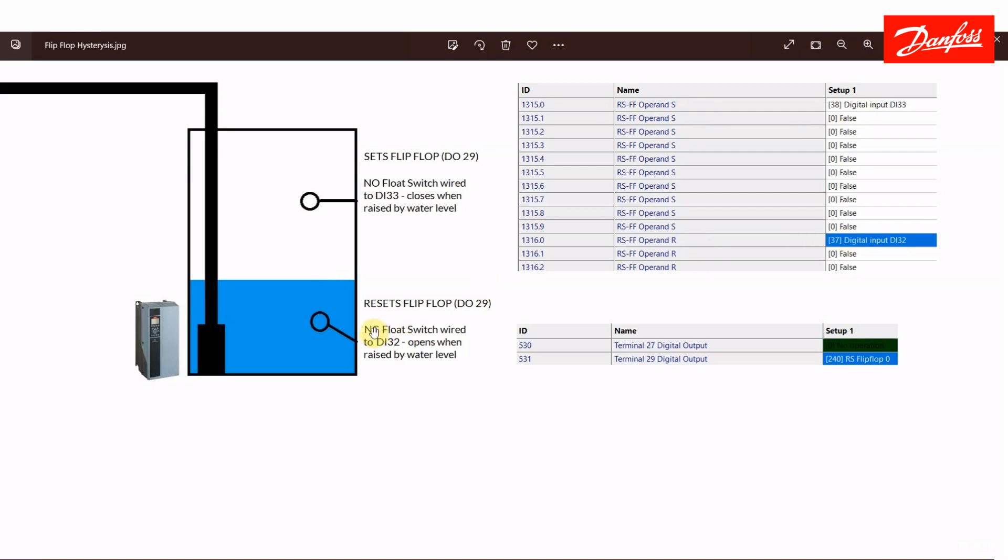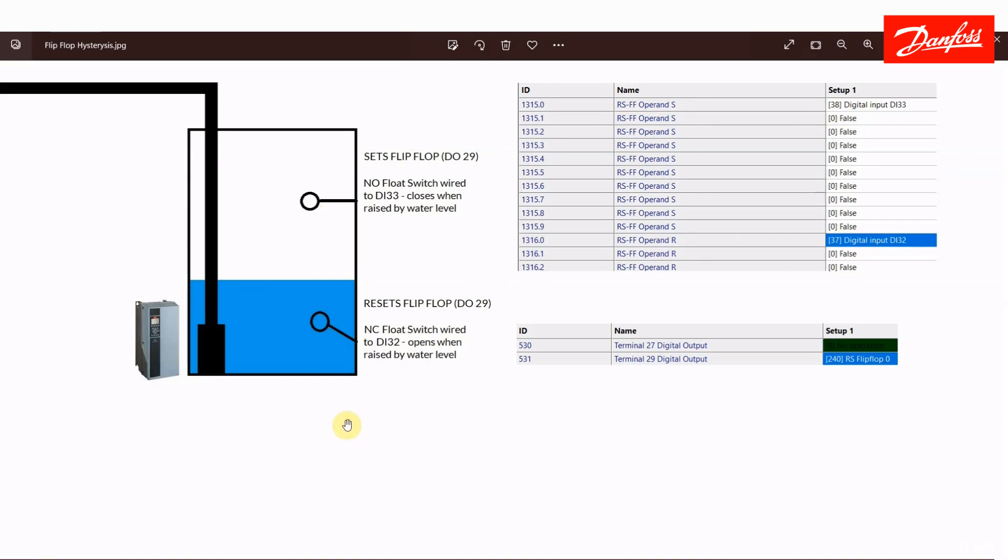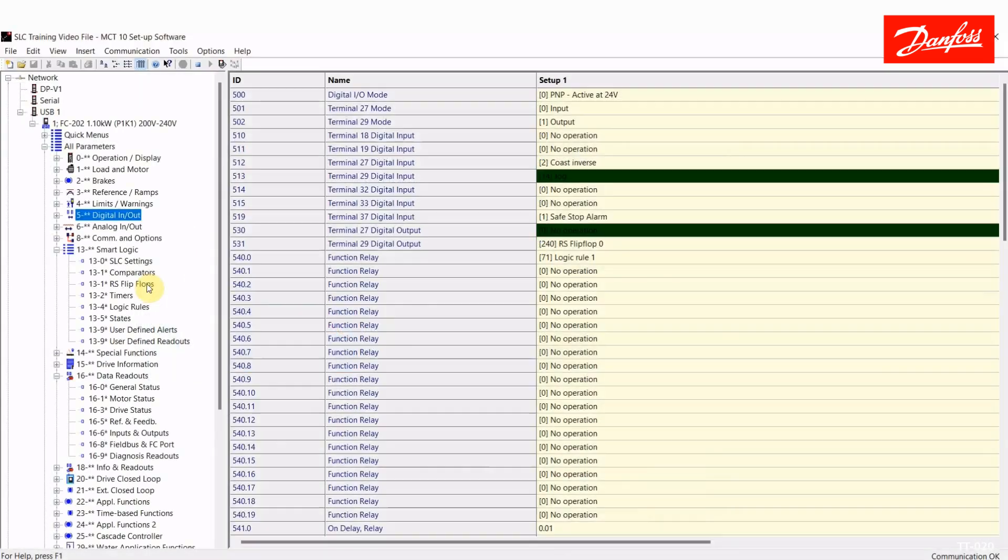So at this point, if the water level raises to this point, this pump is going to come on and bring the tank level down. And to reset the flip flop, I have a normally closed switch here that would be closed when it's in the relaxed position. So as the water level drops and the switch comes to level or the relaxed position, that input would come on and break the latch. So let's take a look at how that works. That's a way for me to create hysteresis. I've turned the pump on at this point and I want it to remain running until I hit this point.